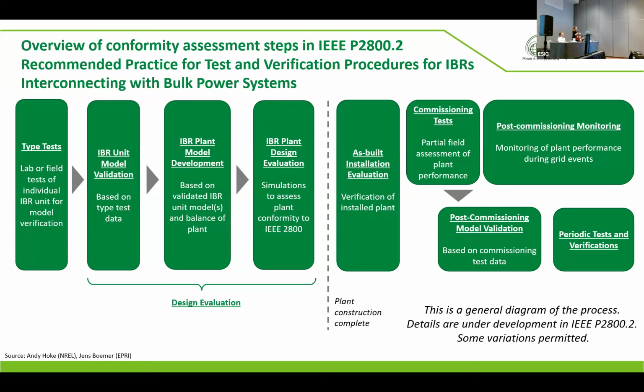So the post-commissioning monitoring part is something that is not happening today, even in areas that have stringent connection requirements. It's basically the plant got connected and you forget about it until a big event happens, and then you are wondering what happened. But with 2800.2, the idea is that you are continuously monitoring the plant, and say if events are happening, and it doesn't have to be a big Odessa event, maybe just your plant tripped once, now you have disturbance recording, and you can actually validate your models for large signal disturbance. And that is the first instance where you can actually do it. And you can also verify if your plant has been conformant with 2800, and you can continuously monitor the plant. And as updates are happening to the plant, some verification also needs to be done. So that's what the post-commissioning part is about.